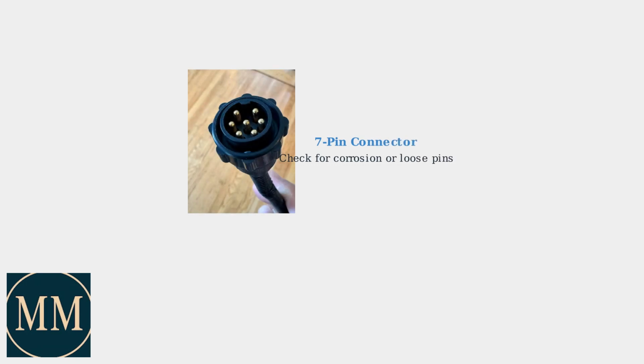The most common cause of the F6E2 error is a poor electrical connection, particularly in the wiring harness that connects the main control board and motor control unit. The wiring harness links the central control unit, or CCU, with the motor control unit, or MCU. Look for the 7-pin connector that handles this critical communication. Examine the 7-pin connector closely. This is where communication between the CCU and MCU occurs, and it's prone to corrosion or loose connections.